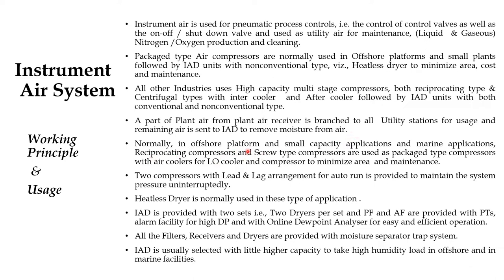Normally in offshore platforms, small capacity applications, and marine applications, reciprocating compressors and screw compressors are used as package type compressors with air coolers to minimize area and maintenance. Normally two compressors with lead and lag arrangement for auto run are provided to maintain the system pressure uninterruptedly in those areas.